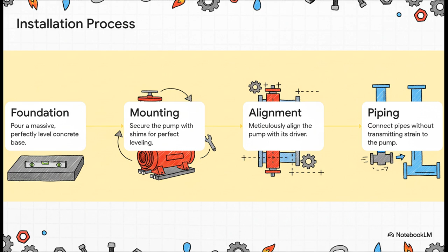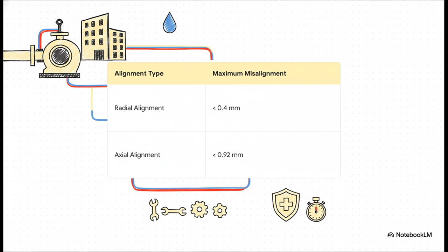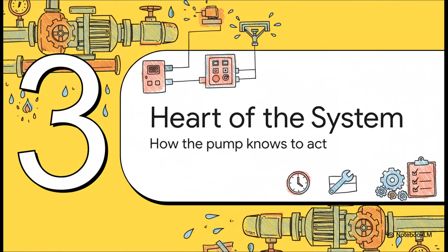And these numbers really tell the story. The radial alignment, that's how centered the two spinning shafts are, has to be off by less than 0.4 of a millimeter. We're talking about the thickness of maybe 4 sheets of paper. That's it. Any more than that, and the incredible forces at play could literally rip the machine apart at the one moment it's needed the most.